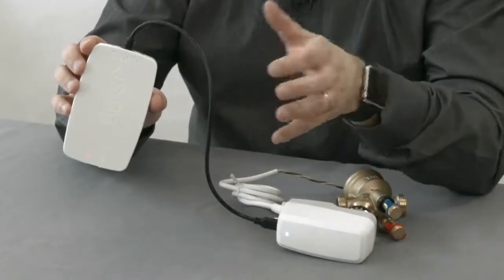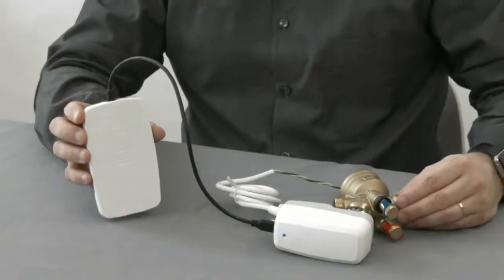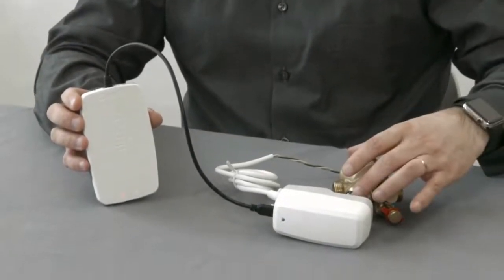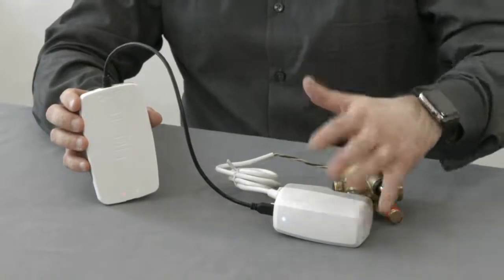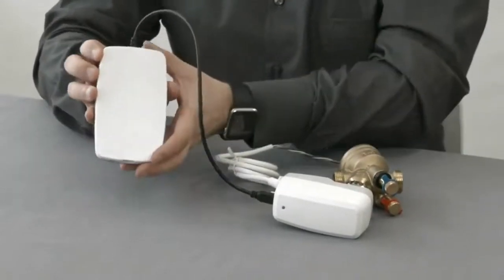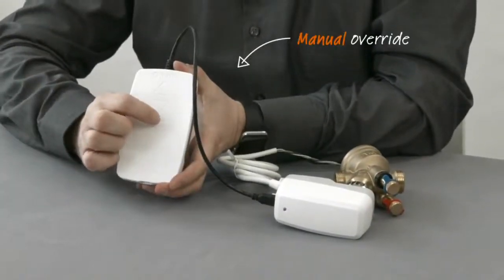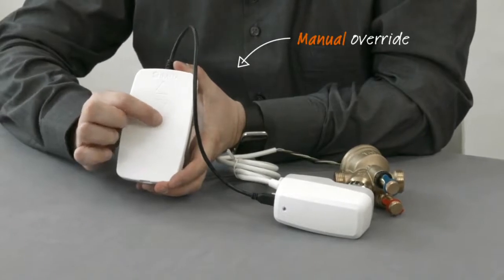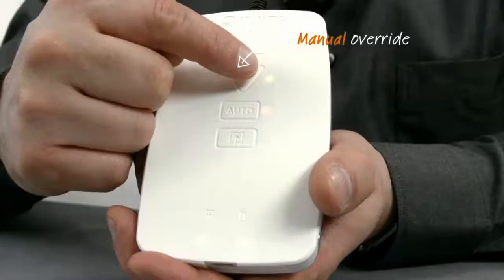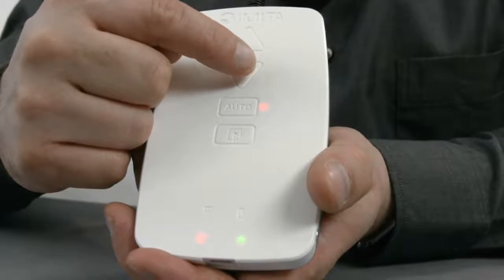For instance, if you want to measure the flow through the valve, you would need the valve to be fully opened, and the easy way to do that with the dongle is simply to press the auto button here to switch to manual mode, as the red LED indicates.